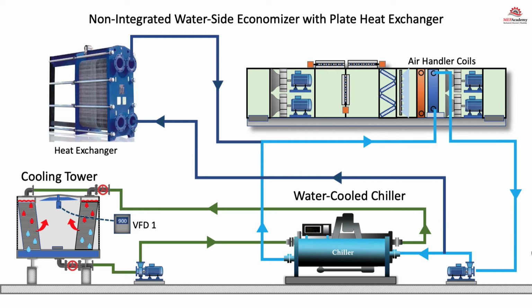Next, we tap into the condenser water supply coming from the cooling tower basin and feeding the chiller. This will be our inlet on the cold side of the heat exchanger. Then, on the cold water outlet of the heat exchanger, we'll connect to the condenser water return piping, leaving the chiller and entering the tower. To make this all work, there needs to be control valves that reroute the water when the economizer is activated. Remember, this is a non-integrated economizer, so there is no simultaneous running of the chiller. This is why the piping is routed around the chiller.